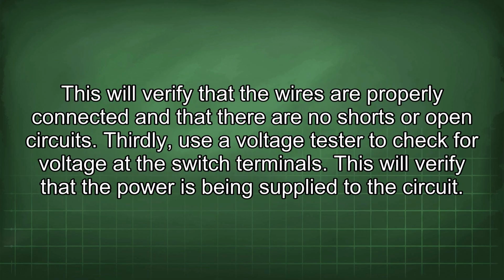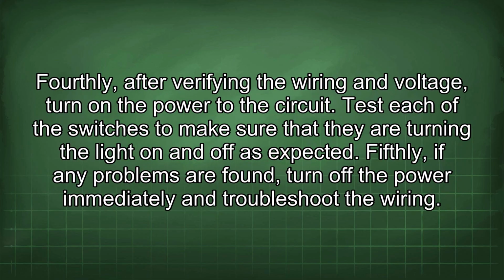This will verify that the wires are properly connected and that there are no shorts or open circuits. Thirdly, use a voltage tester to check for voltage at the switch terminals. This will verify that the power is being supplied to the circuit. Fourthly, after verifying the wiring and voltage, turn on the power to the circuit. Test each of the switches to make sure that they are turning the light on and off as expected.